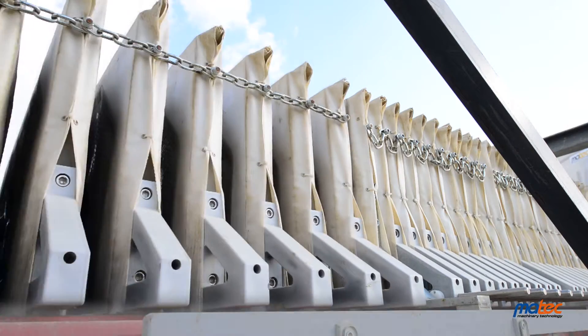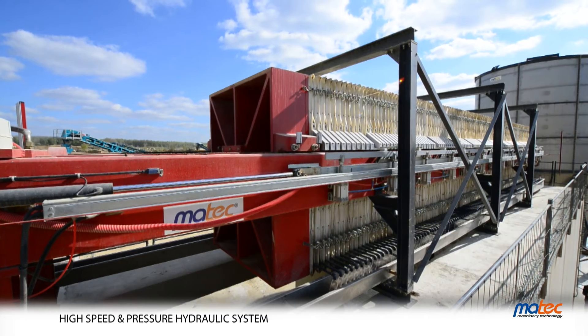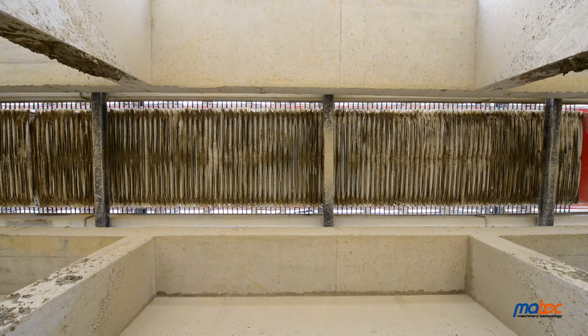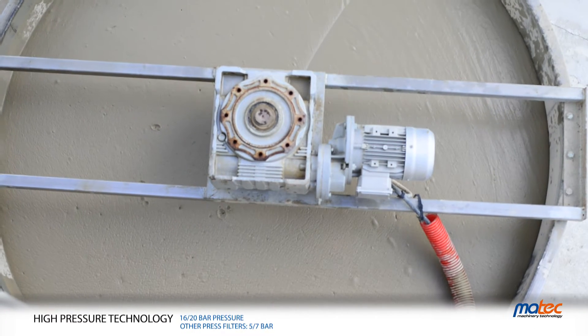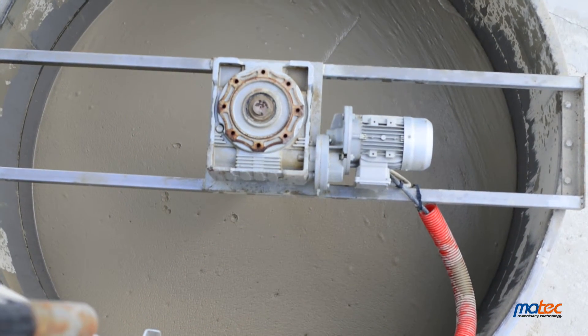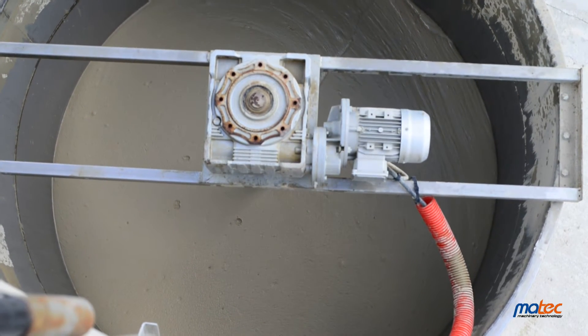The cycle begins with the control unit that closes the plates and keeps the chambers closed. At this point, working pressure reaches 350 bars, to resist the counter pressure created by the mud feeding pump. Once every plate is closed, the feeding pump starts filling the chambers. The HPT double or triple case pump sucks the mud from the homogenizer tank and pumps it inside the filter press.